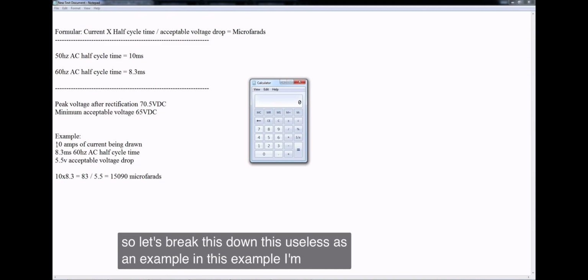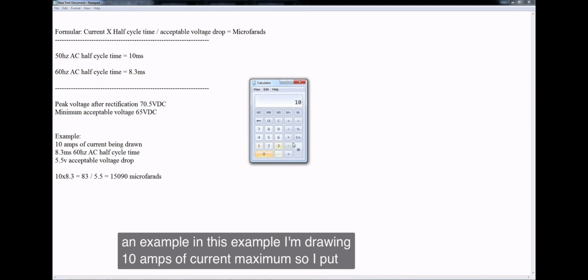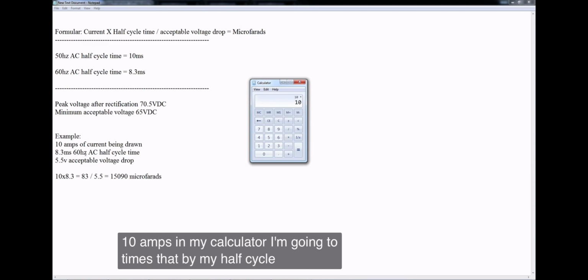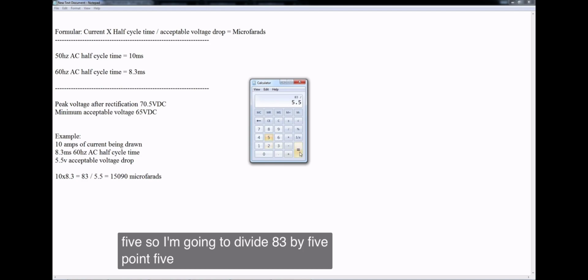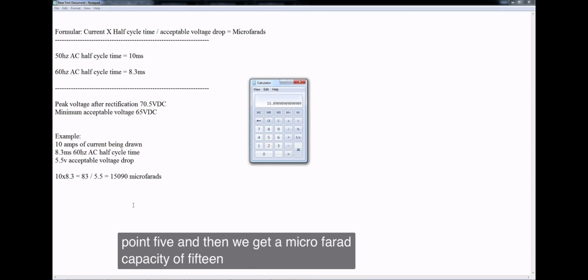In this example, I'm drawing 10 amps of current maximum, so I'll put in 10 amps in my calculator. I'm going to times that by my half cycle time, so in this example I'm going to use 8.3, so times it by 8.3, hit equals, and then my acceptable voltage drop is 5.5, so I'm going to divide 83 by 5.5, and then we get a microfarad capacity of 15,090 microfarads.